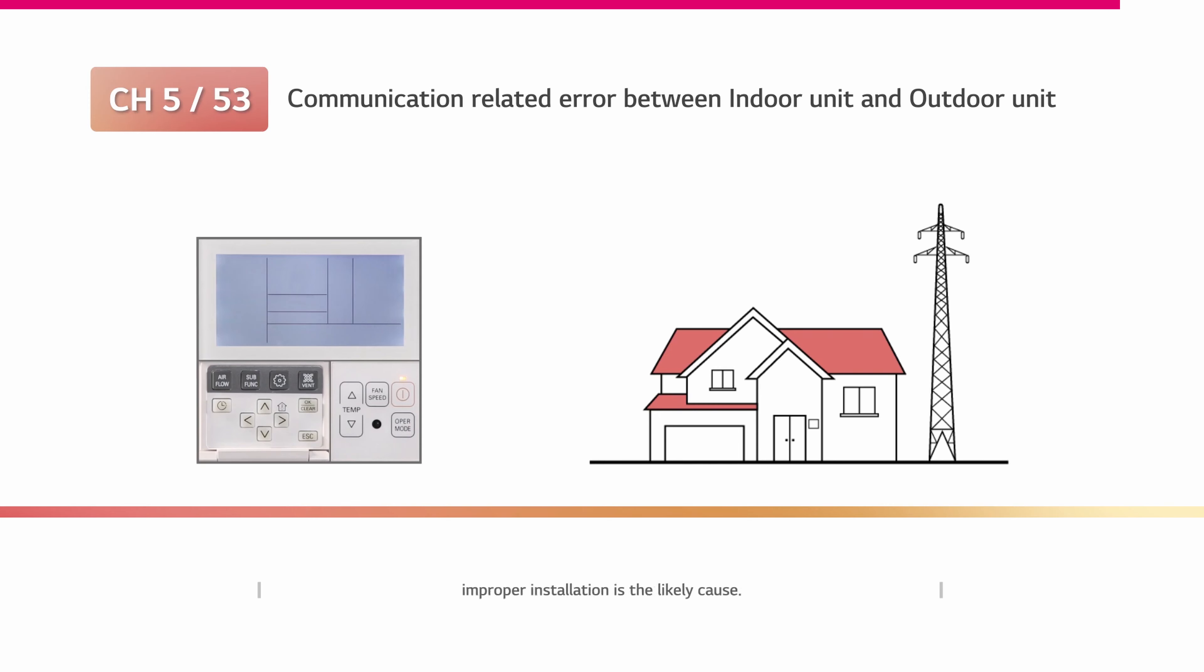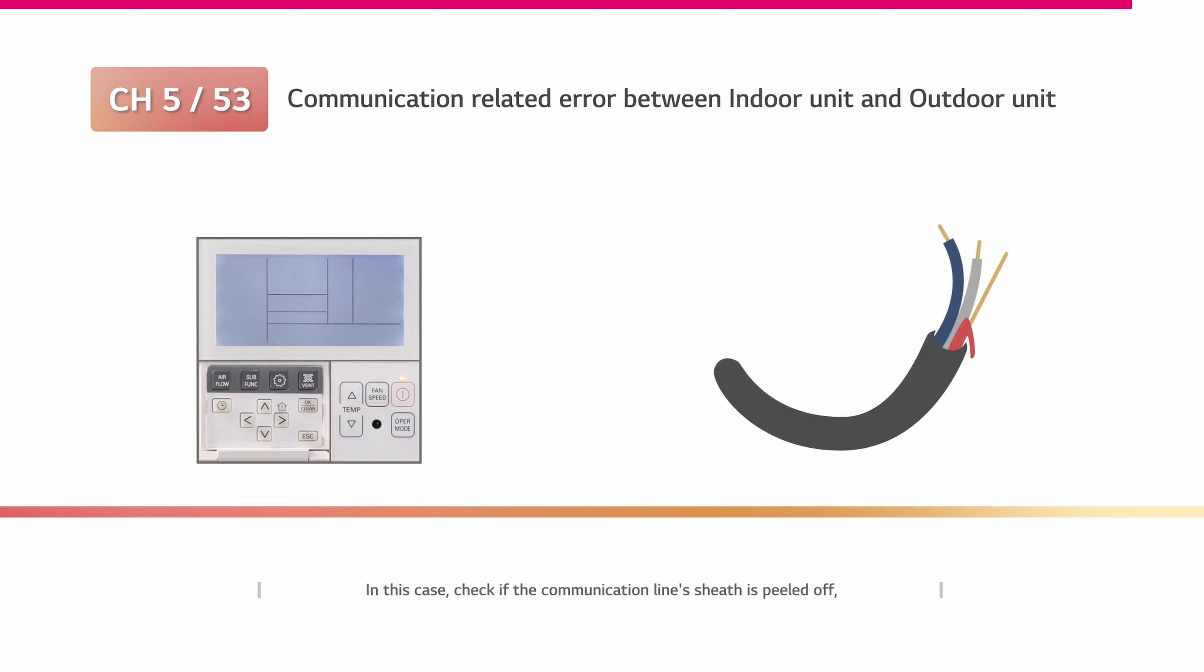In this case, check if the communication line's sheath is peeled off, disconnected or has short-circuited and replace the line if an error is found.